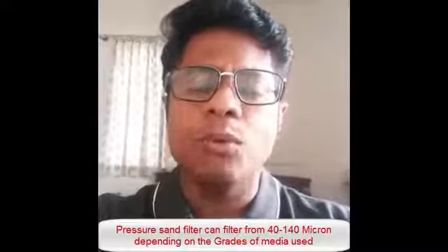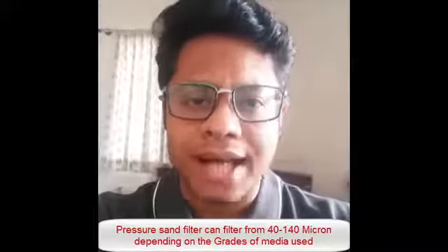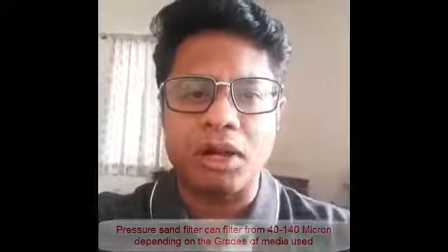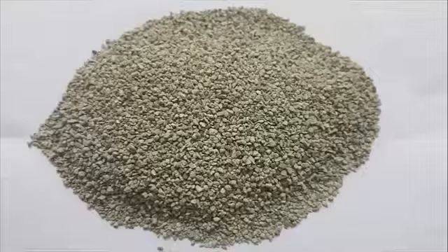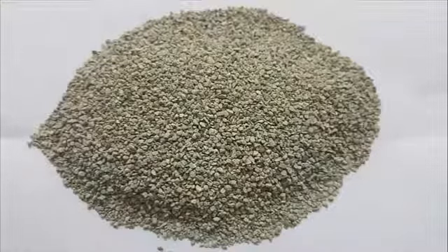The normal sand filter does filtration up to 140 micron. A strand of hair is around 130 to 140 micron, so it should be able to filter hair and small particles. If you want finer filtration, there are materials like Next media, which is used to reduce the turbidity further. If you have total suspended solids, you need different kinds of materials. So the first cylinder is the sand filter.